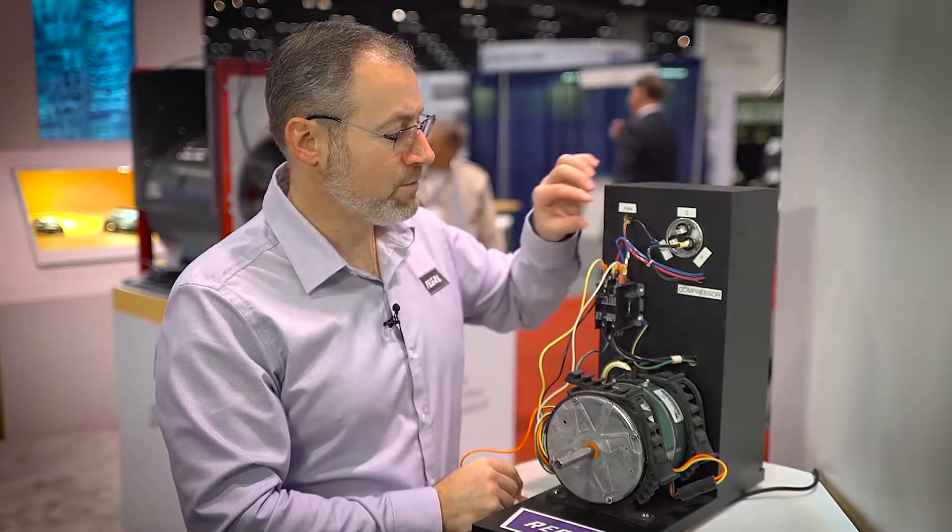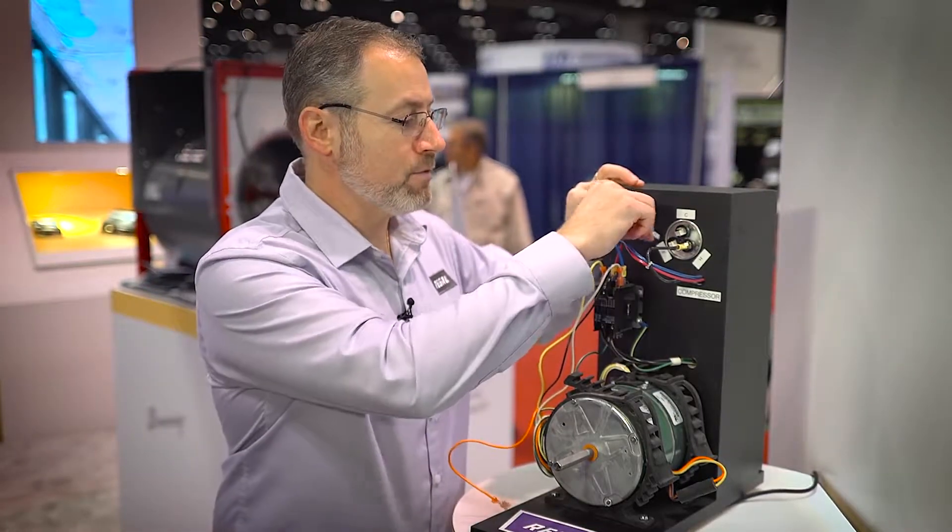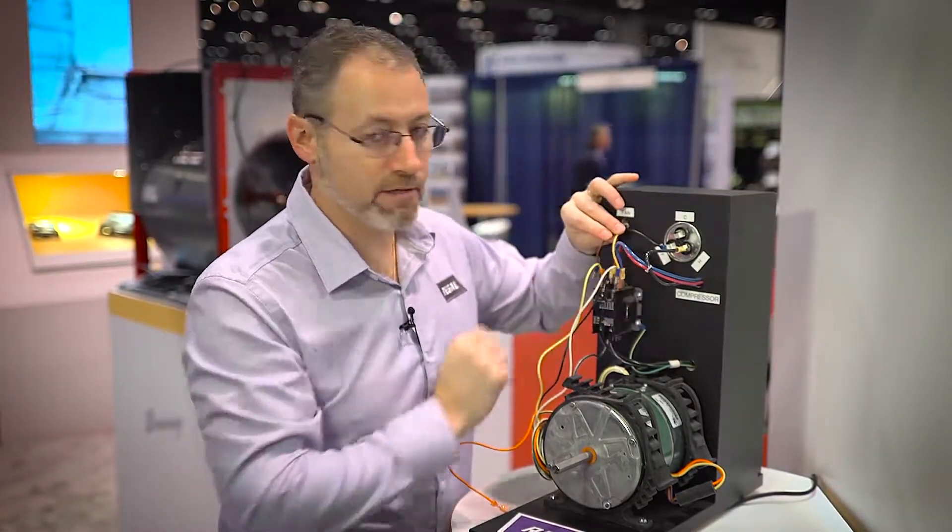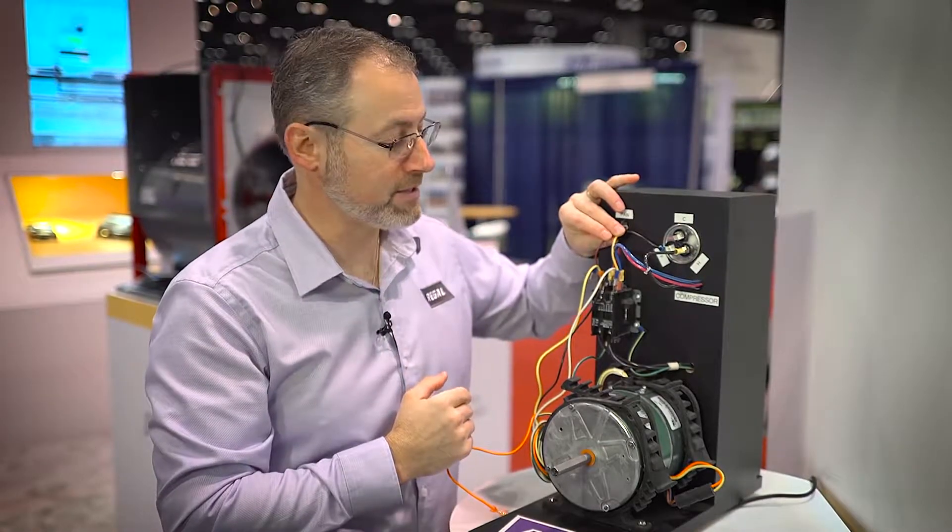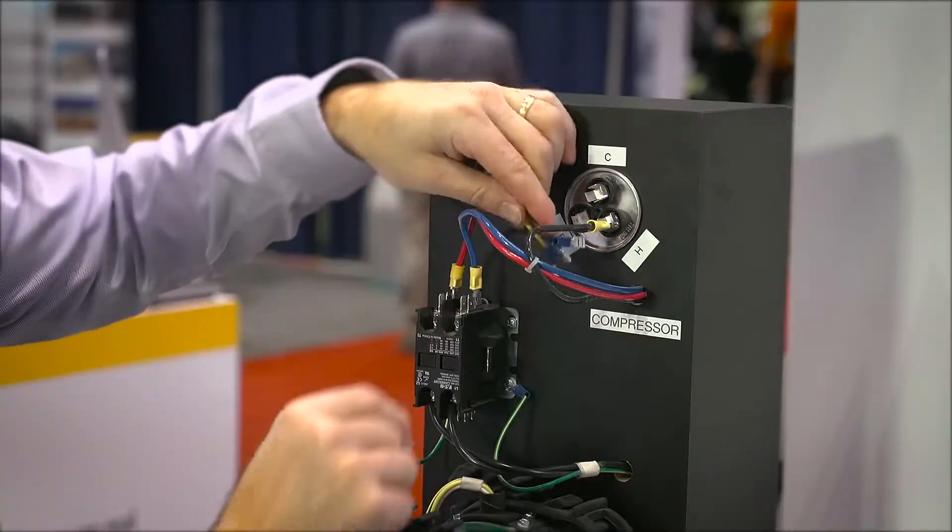On this unit we see that the fan motor, in this case a PSC, would be connected to the capacitor and connected to either side of the contactor. So first we would remove that motor by disconnecting the wires from the contactor and disconnecting the wires from the capacitor.